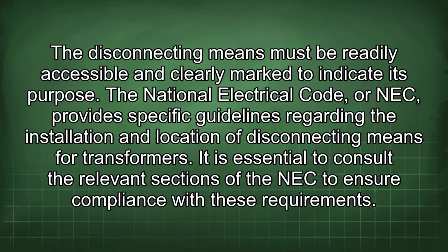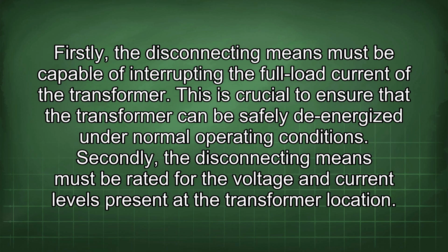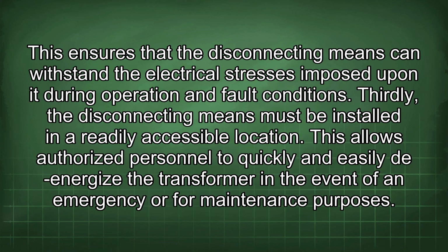The National Electrical Code, or NEC, provides specific guidelines regarding the installation and location of disconnecting means for transformers. It is essential to consult the relevant sections of the NEC to ensure compliance with these requirements. Firstly, the disconnecting means must be capable of interrupting the full load current of the transformer. This is crucial to ensure that the transformer can be safely de-energized under normal operating conditions. Secondly, the disconnecting means must be rated for the voltage and current levels present at the transformer location. This ensures that the disconnecting means can withstand the electrical stresses imposed upon it during operation and fault conditions.